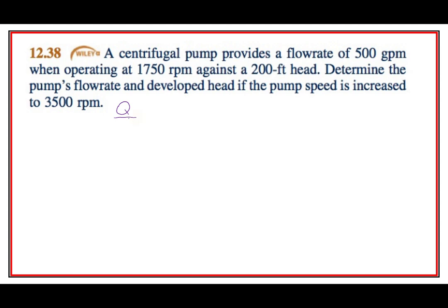So what we'll use here, if we have the same pump, is the same diameter. So what we can say is we have a relationship between the flow rate, which I'm going to call Q, a lot of times I'll have that V dot with a cross out, but here we go. And by this I mean that 1 is the new pump speed, and 2 is the old pump speed. Could have chosen either one, doesn't matter.